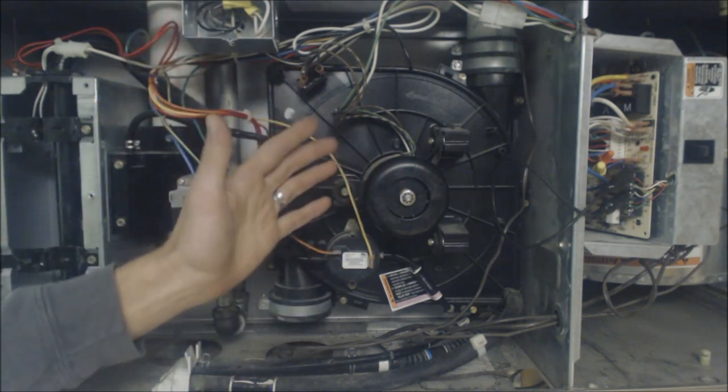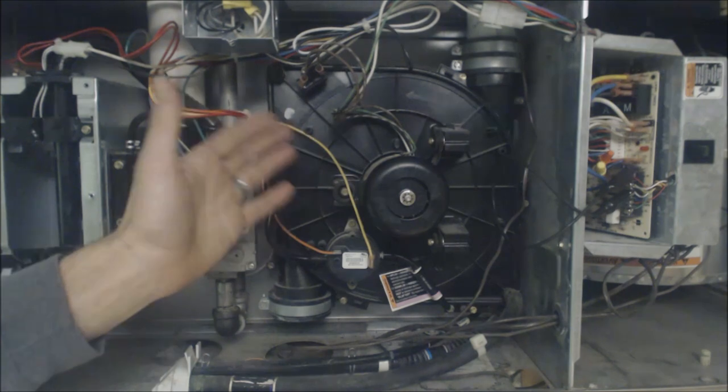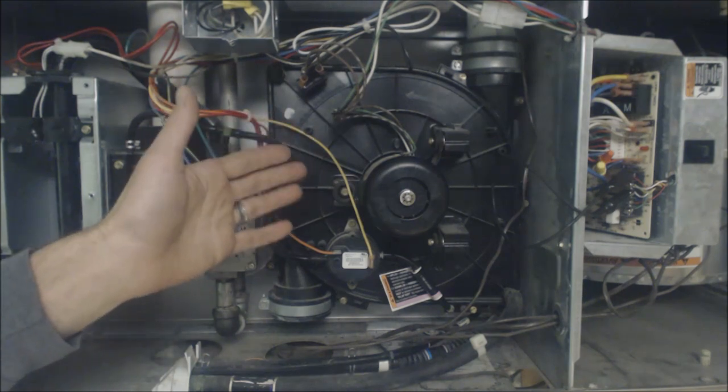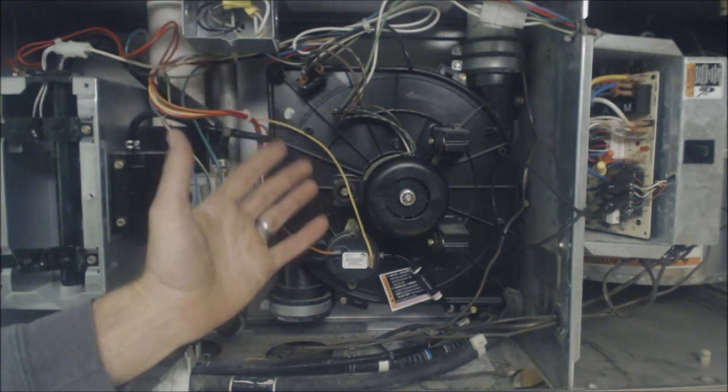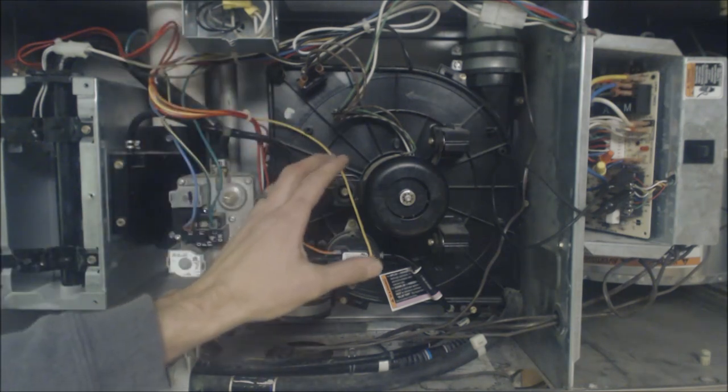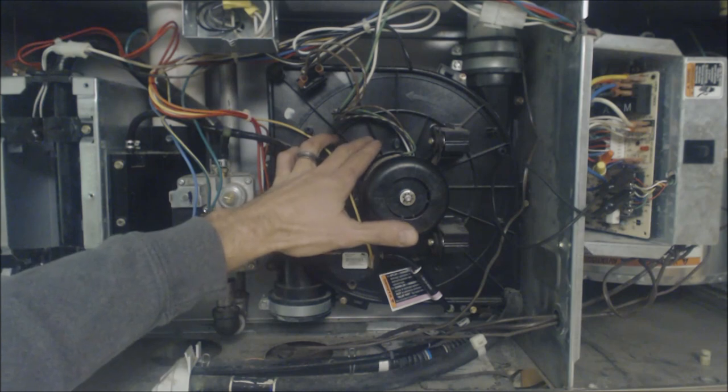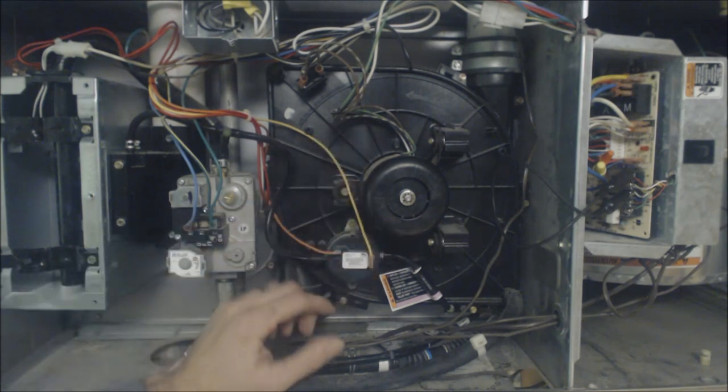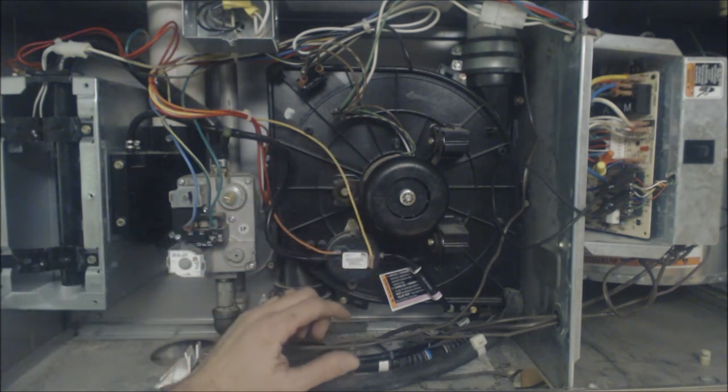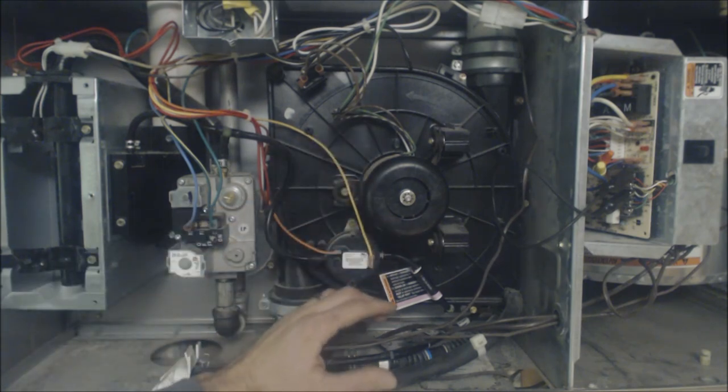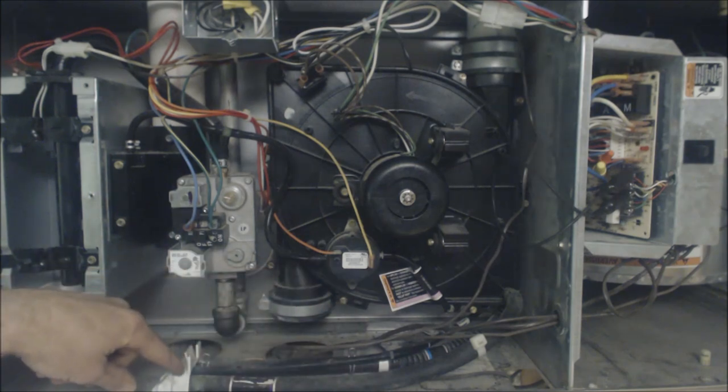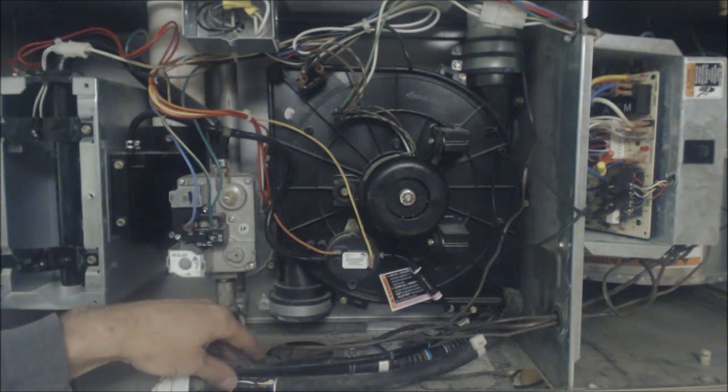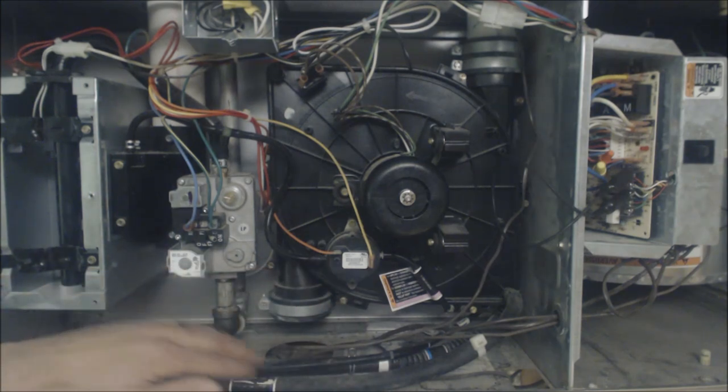So some of these wheels inside are made with plastic unfortunately sometimes and they're falling apart, okay, so that means that this needs to get replaced. But it could be that the condensate drain is clogged, okay, and the water is backing up in these tubes right here.